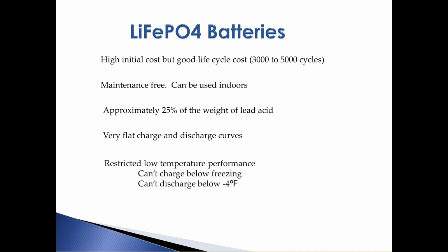One of the downsides is they do have restricted temperature performance, particularly low temperature when compared to lead acid. They also have a high temperature limit, but it's significantly up there. You're probably not going to run into that. You can't charge most of them below freezing. Somewhere in the range of 25 to 30 degrees is their cutoff point for being able to accept a charge. And you can't discharge them sometimes below numbers as high as -4F, or some of them down to -25F now.